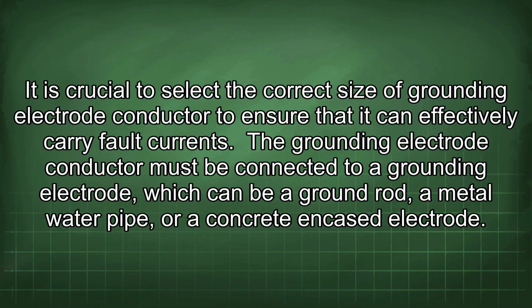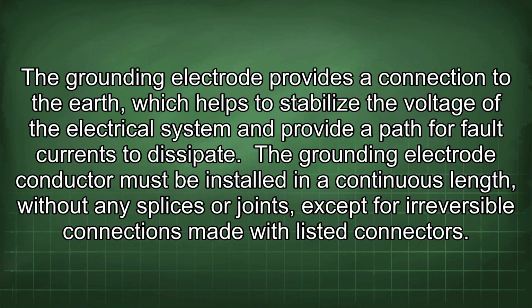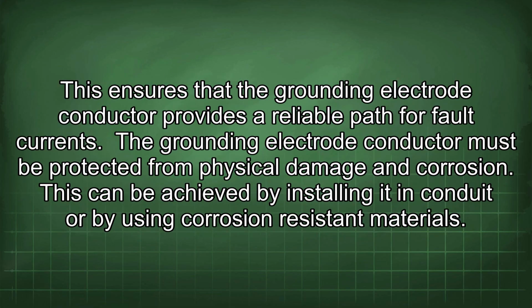The grounding electrode conductor must be connected to a grounding electrode, which can be a ground rod, a metal water pipe, or a concrete encased electrode. The grounding electrode provides a connection to the earth, which helps to stabilize the voltage of the electrical system and provide a path for fault currents to dissipate. The grounding electrode conductor must be installed in a continuous length, without any splices or joints except for irreversible connections made with listed connectors. This ensures that the grounding electrode conductor provides a reliable path for fault currents.